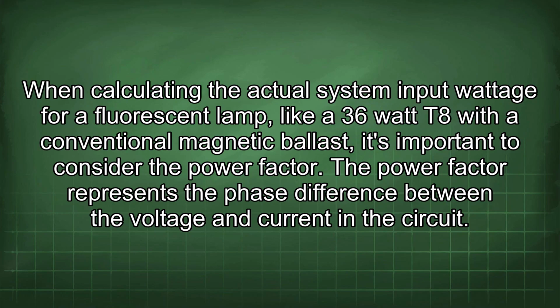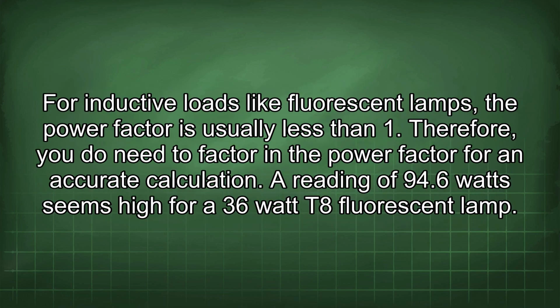When calculating the actual system input wattage for a fluorescent lamp, like a 36 watt T8 with a conventional magnetic ballast, it's important to consider the power factor. The power factor represents the phase difference between the voltage and current in the circuit. For inductive loads like fluorescent lamps, the power factor is usually less than 1. Therefore, you do need to factor in the power factor for an accurate calculation.